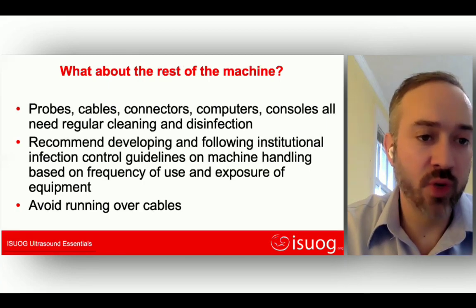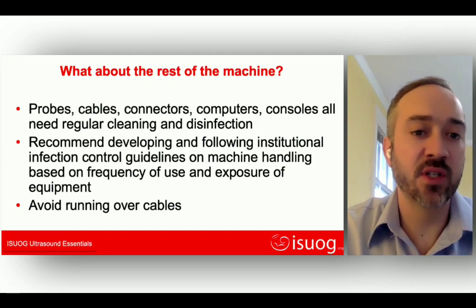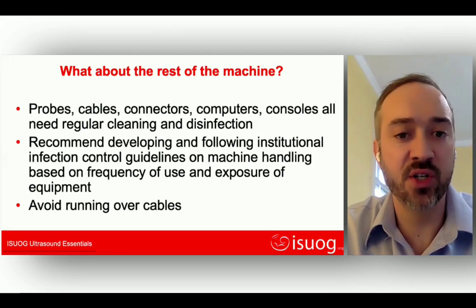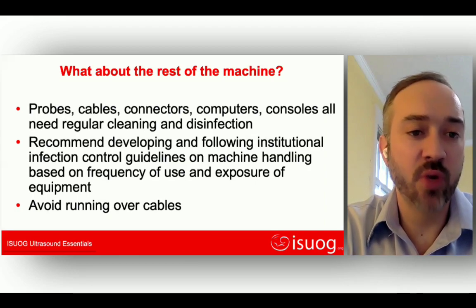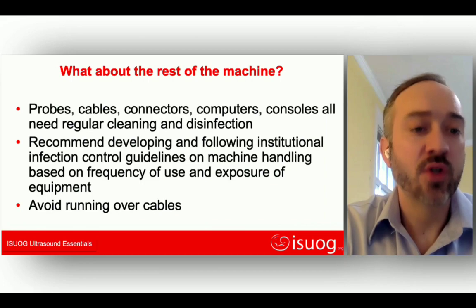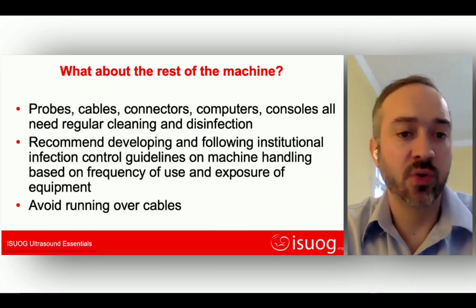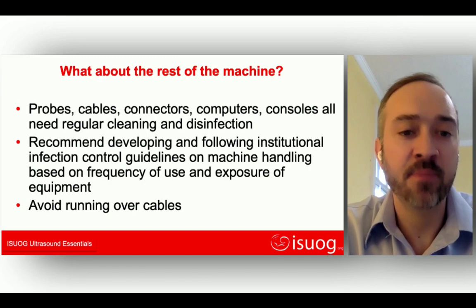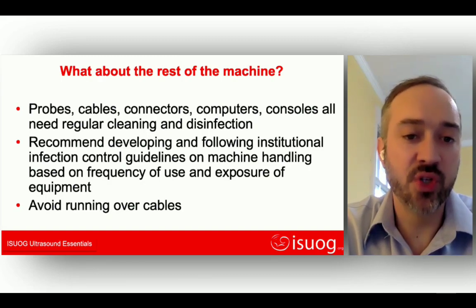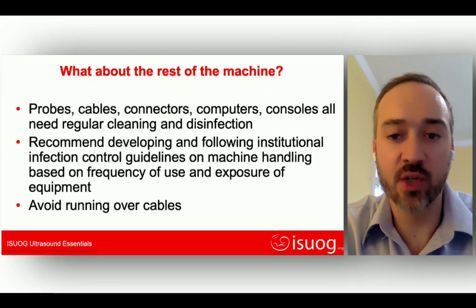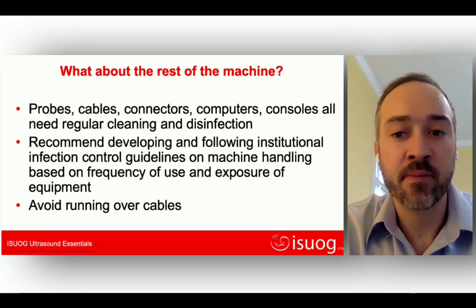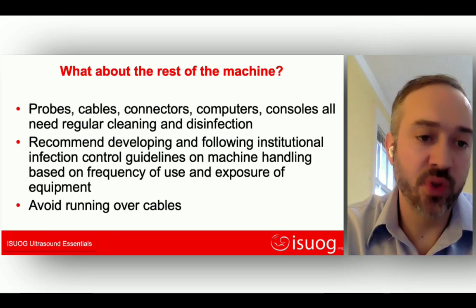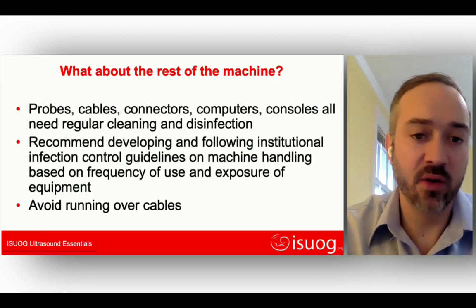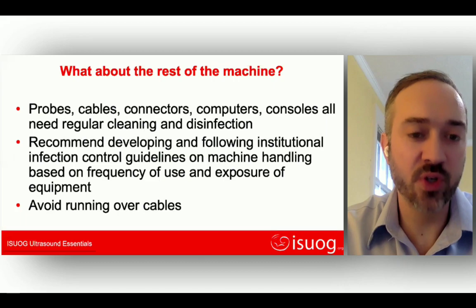And in terms of the rest of the machine, don't forget that this is a complex unit with probes, cables, connections, computers, consoles. These all need regular cleaning and disinfection. So we'd recommend developing and following institutional infection control guidelines on the machine, and do this based on the frequency and use and handling of the exposure of the equipment. Like Angela was saying, think about what you do between patients, but also at the end of the day, weekly or monthly, depending on how often the machine is used and what you need to do to maintain it. And obviously avoid running over the cables. This can damage the fiber optics.